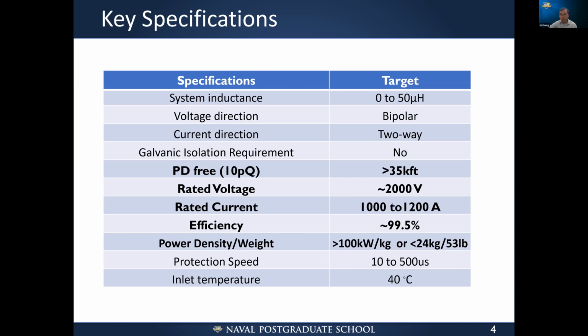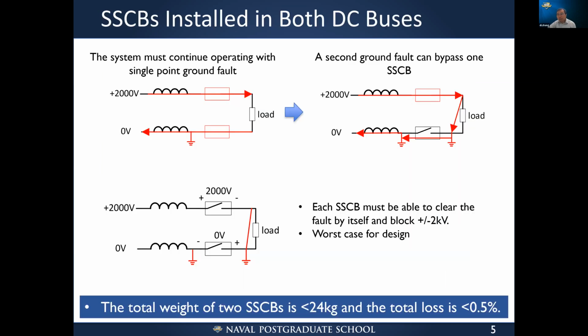The efficiency is 99.5%, and the power density is higher than 100 kilowatts per kilogram, or the total weight must be less than 24 kilograms, or 53 pounds. Right? And the response speed is 10 to 500 microseconds, and there's also some cooling requirement. So one thing I want to emphasize is that solid state circuit breakers need to be installed in both DC buses, right? Because this is a critical system.